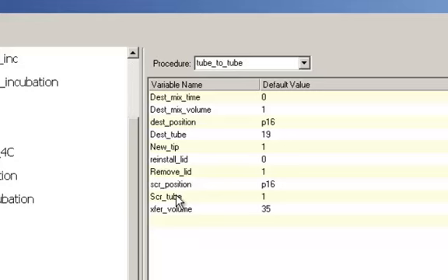The method or the procedure also selects the appropriate tip. If you tell it you're going to make the master mixes on the deck, have the instrument make them, it's going to put up a different instrument setup that has some P1000 tips, P250s, and I believe P50s, and it's going to choose the appropriate tip according to the volume that it has to transfer.